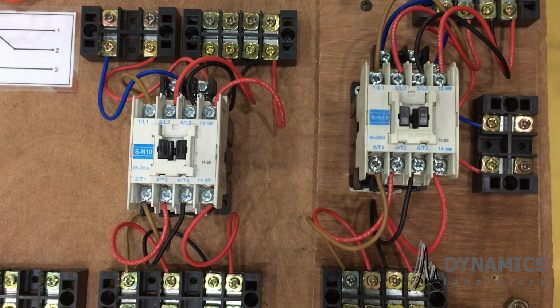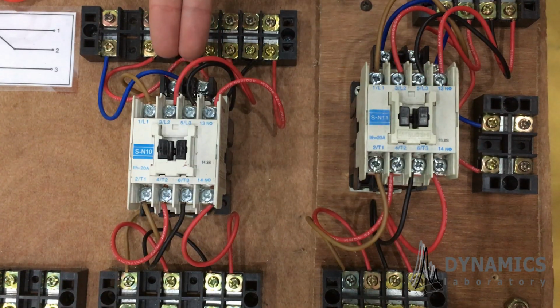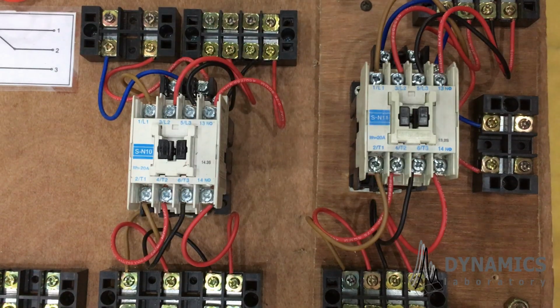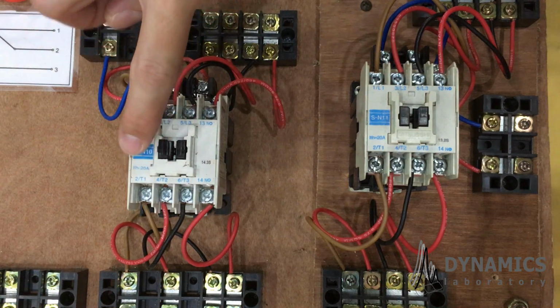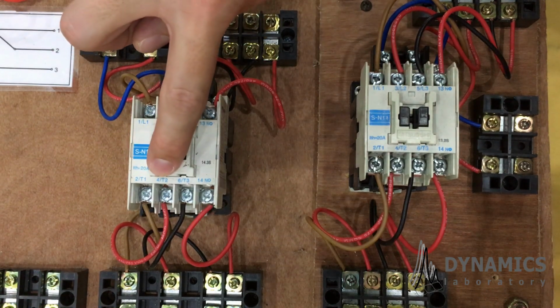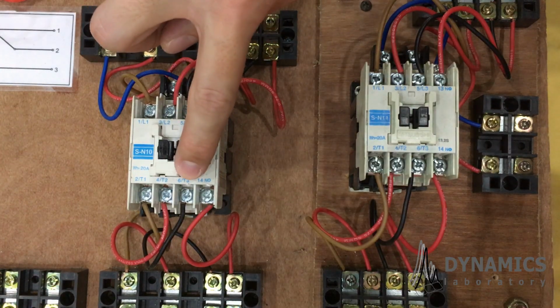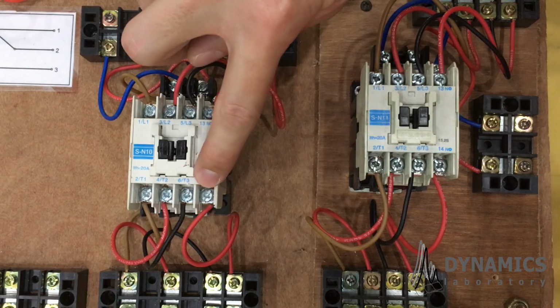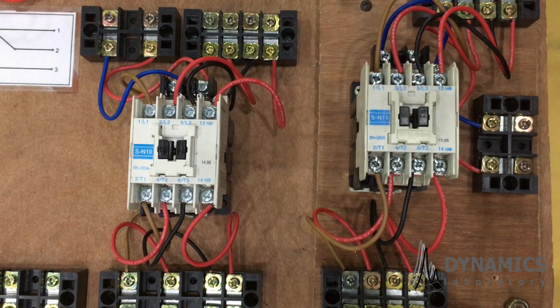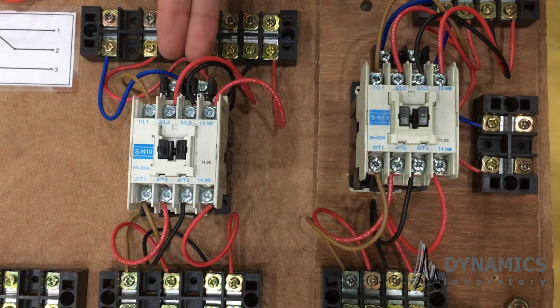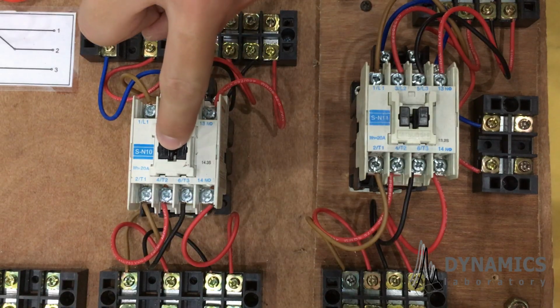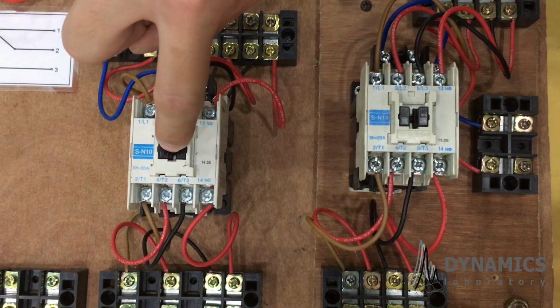The normal condition of this switch is normally open. But if the coil is energized, then all switches change to the normally closed condition. Terminal 1 and terminal 2 are connected, terminal 3 and terminal 4 are connected, terminal 5, terminal 6, and also terminal 13 and terminal 14 are connected. Let's try it. If the coil is energized, then the black component in here is going down. Like this.